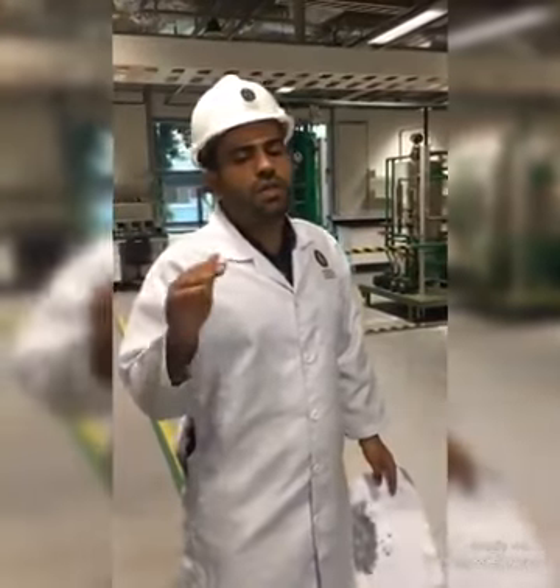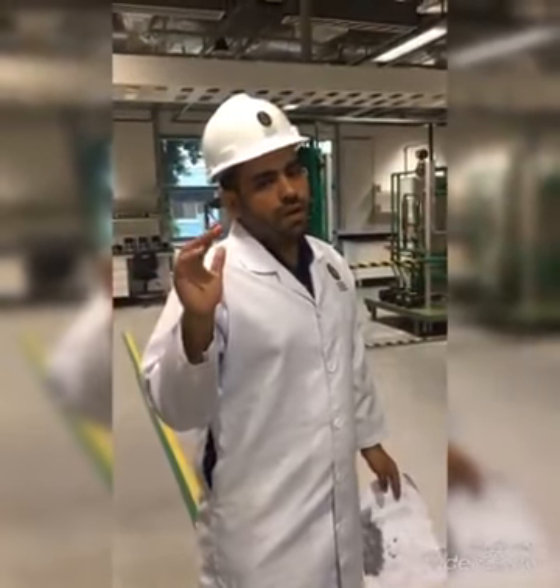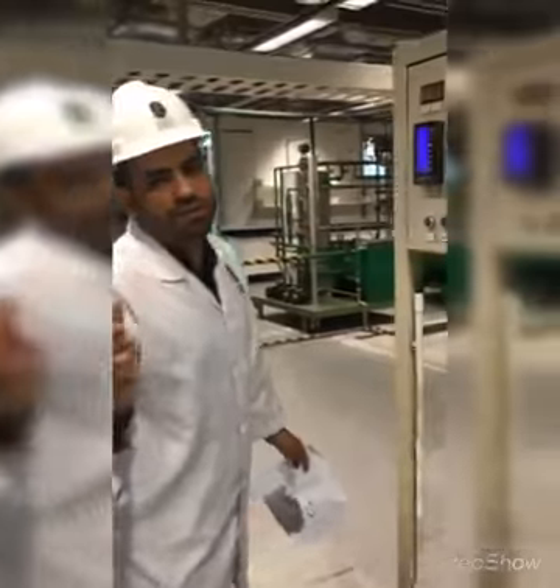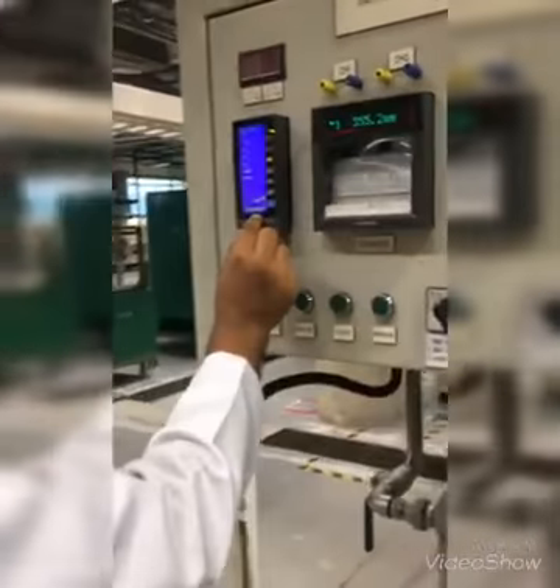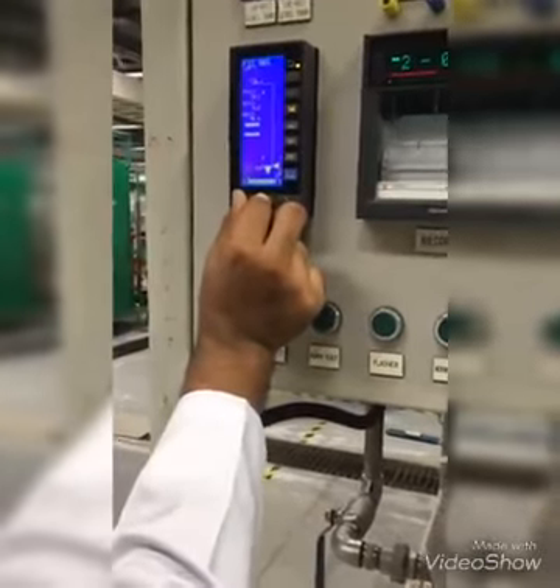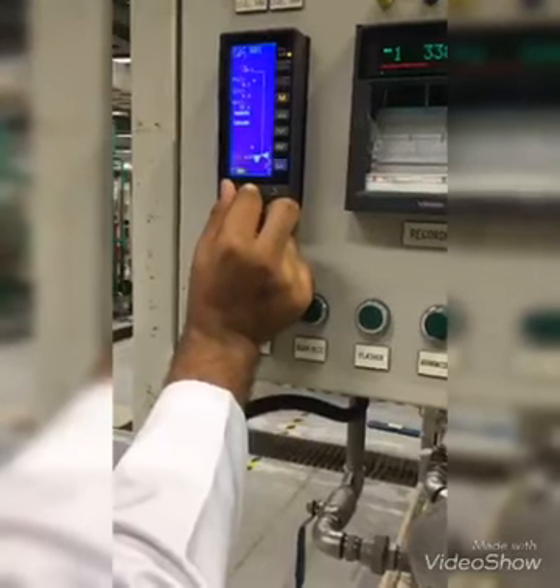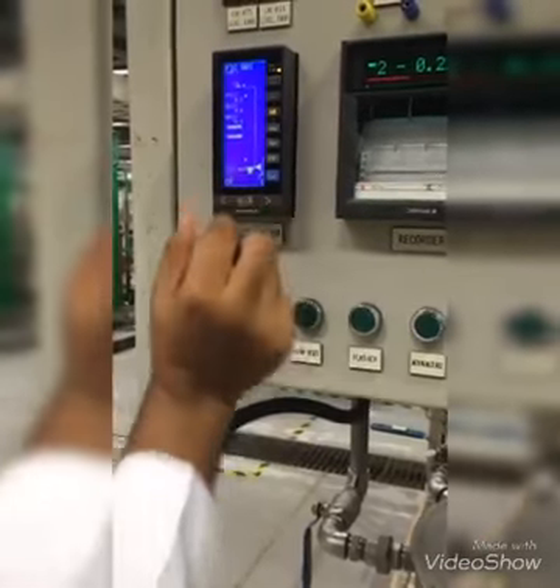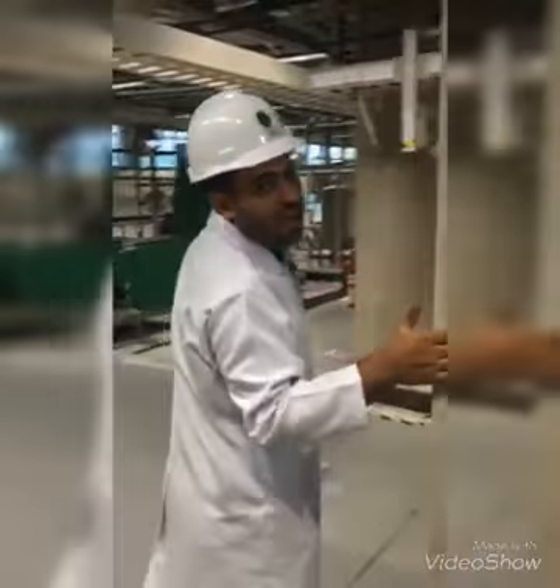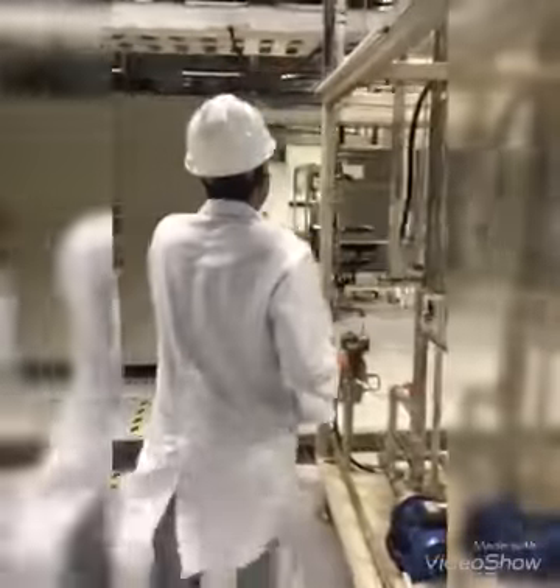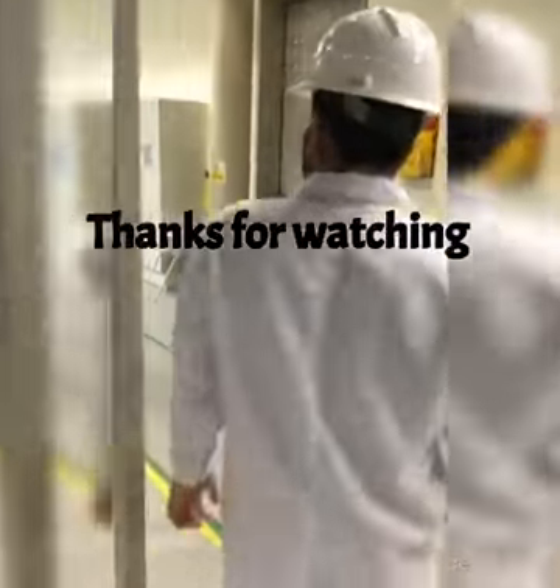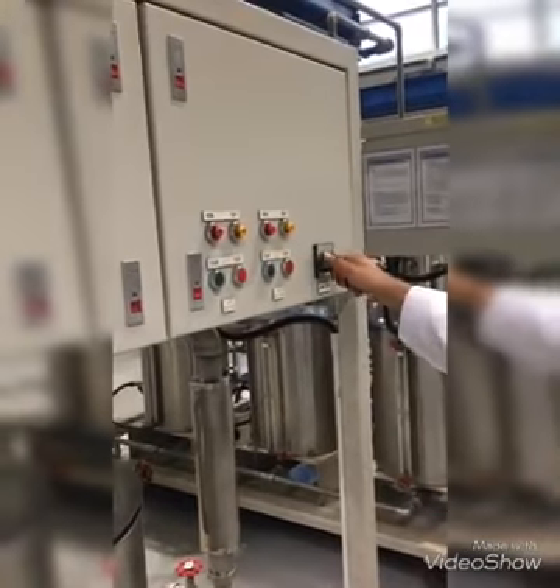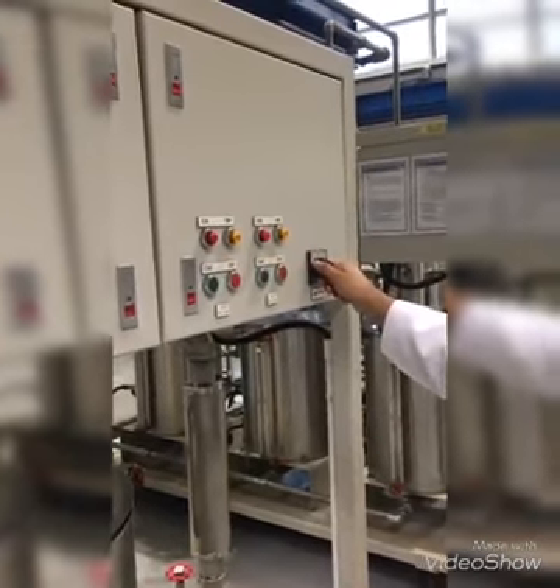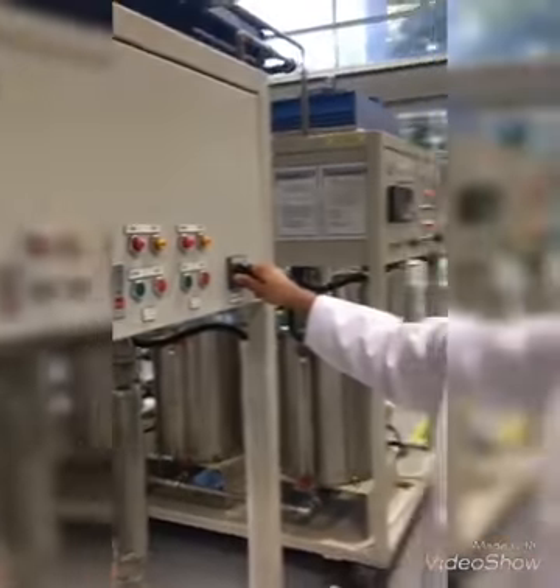Okay, now for the closing up procedures, you need to make sure that the manipulating value is in minus. You go like this one. Try to make sure the manipulating value is in minus. And also go back and close the pressure regulator. And also now switch off the pump, then close off the main panel. That's it.